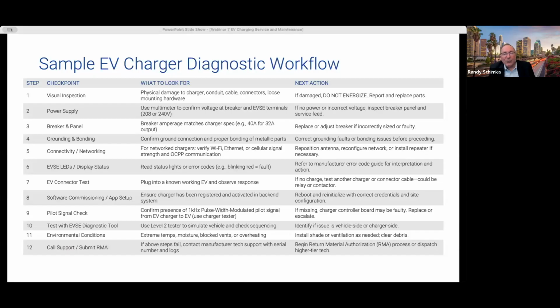So on this page, we have a sample EV charger diagnostic workflow. It's all about systematically pinpointing and fixing issues to keep chargers running smoothly. In this table, we have a 12-step process that covers everything from physical checks to software and environmental factors. You'll start by inspecting for visible damage, verifying power and grounding, and ensuring network connectivity. Then it's about testing components like connectors, using tools like multimeters or testers to catch faults. If issues persist, leverage diagnostic apps and manufacturer support for deeper troubleshooting or return material authorizations to replace parts. Throughout, you're checking for things like voltage stability, error codes, or environmental issues like heat or moisture. This structured approach ensures quick, effective repairs while minimizing downtime for EV drivers.